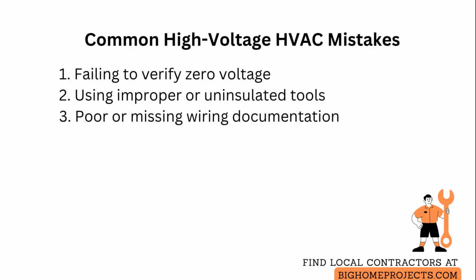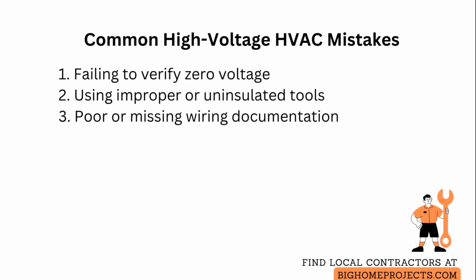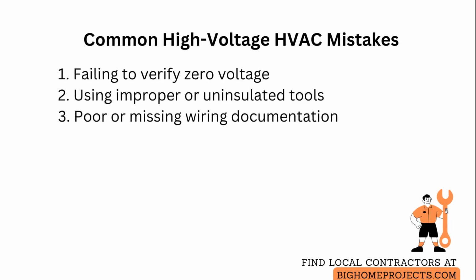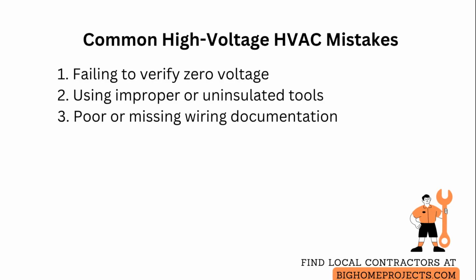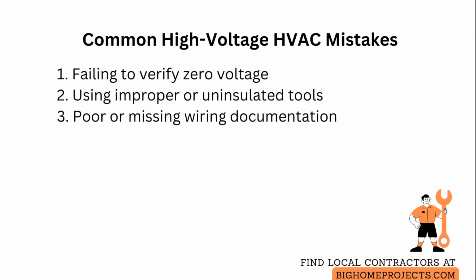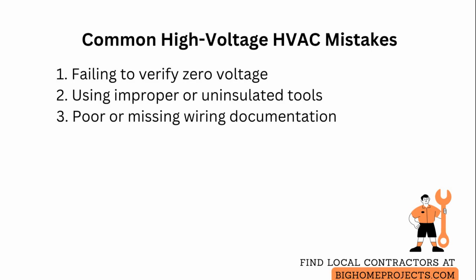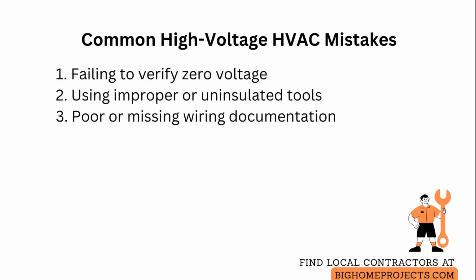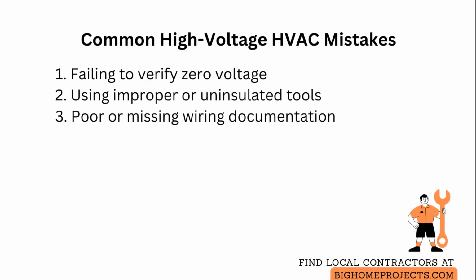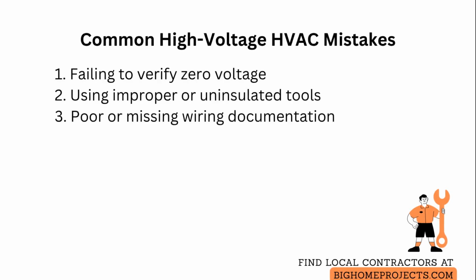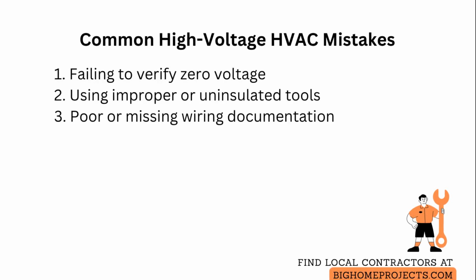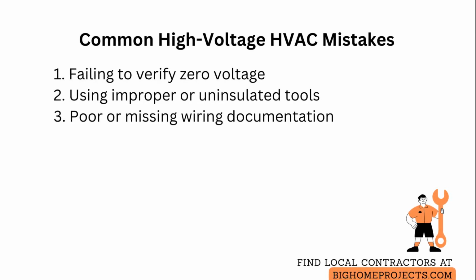The most common mistakes are failing to fully de-energize and verify zero voltage, which can be avoided by always testing at the device terminals after turning off breakers and applying lockout and tagout. Another frequent issue is using the wrong tools or no insulation on tools. So use tools with the correct voltage rating and maintain insulated handles free of damage.